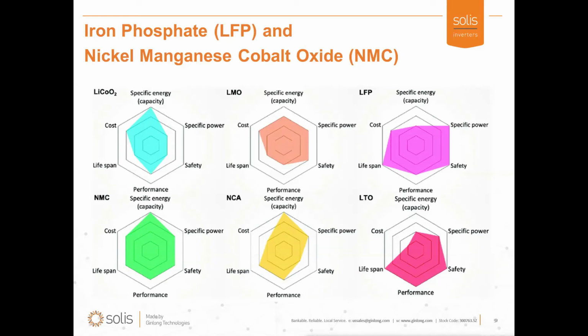Iron phosphate is ideal for ground-mounted energy storage systems. First, LFP batteries are less susceptible to thermal runaway and aren't as dangerous when damaged compared to NMC. LFP batteries also have a longer lifespan than cobalt oxide and are less toxic. In stationary applications, weight isn't much of an issue, so iron phosphate is the ideal choice.